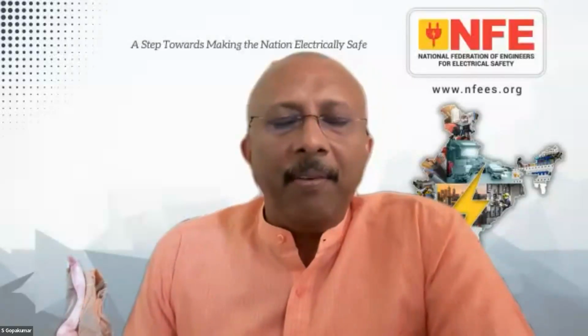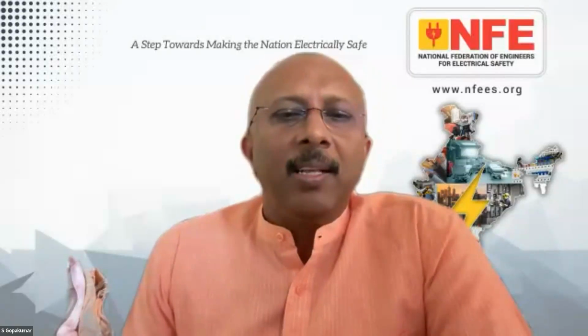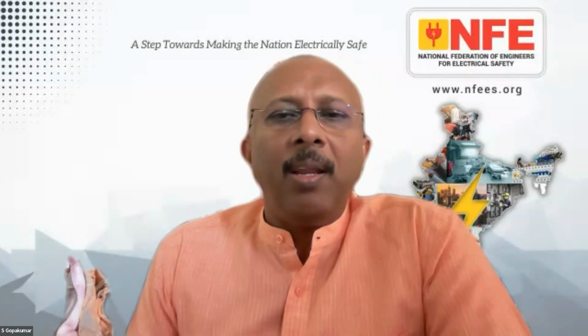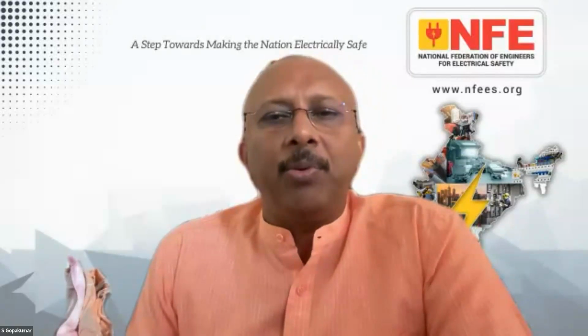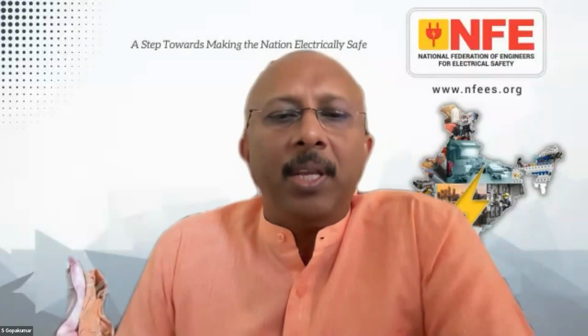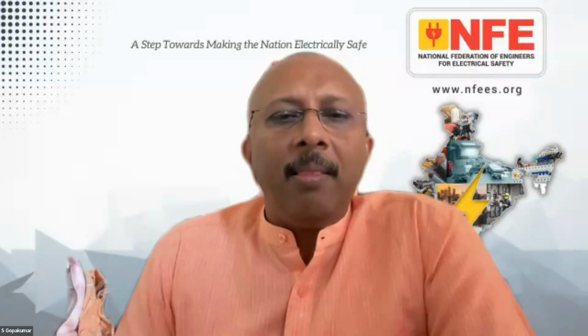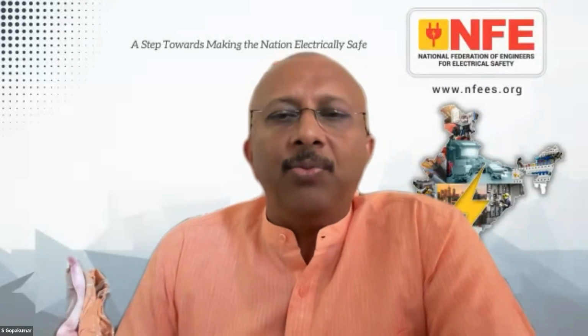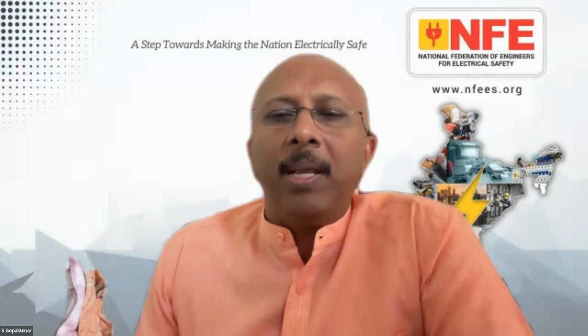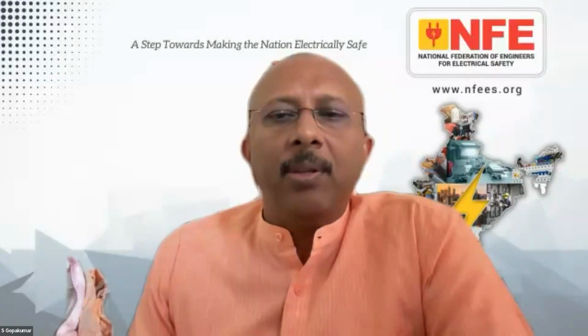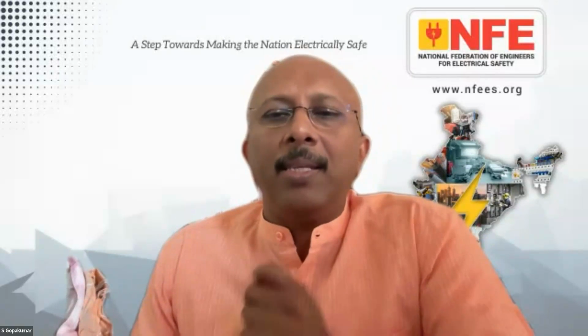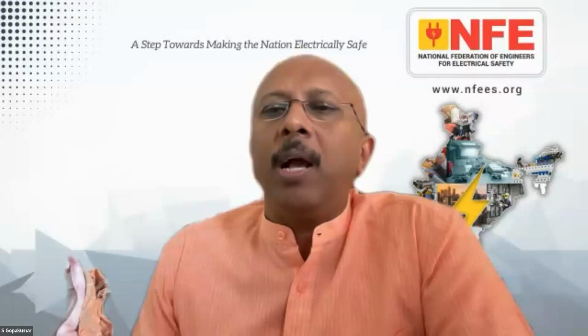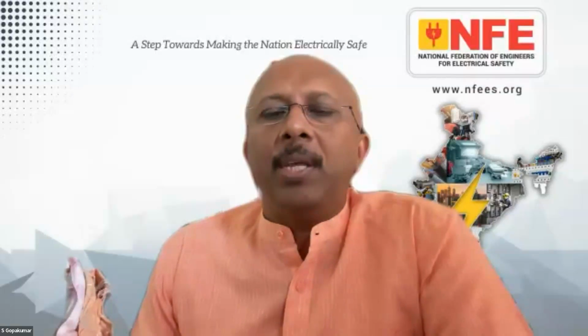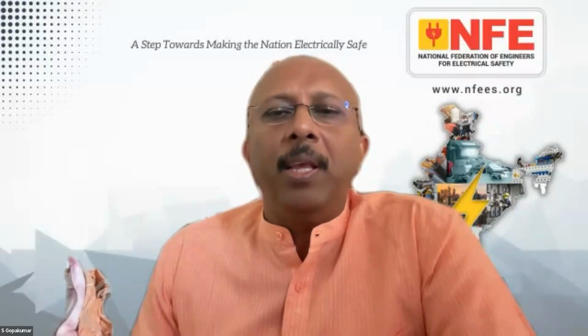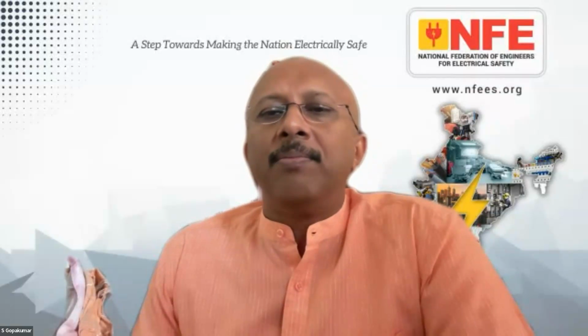Yeah. Actually, every engineer should understand that earthing means there shall be a metallic fault return path to the neutral of the source, the respective source. It is not like, as we colloquially say, fault current goes to earth. That earth is the neutral of the source. That earth is not the soil which we are living on. So we must understand that, and we have to make a metallic fault return path back to the neutral. Then automatically your MCB trips. RCDs may not be required for fault protection, but for the car, of course, yes, that is already provided. But I would request that type A RCDs may be required if the lights are LED or semiconductor based.